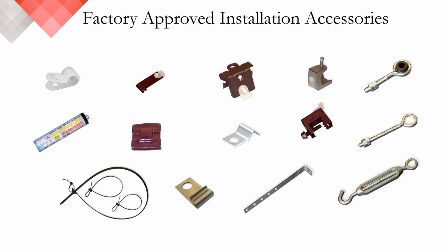The Protectowire company offers an assortment of approved fasteners and splicing devices to facilitate installation for both standard and special applications. Approved fasteners are generally designed to lightly clamp the detector, which enables the tension to be applied progressively. This method is better than arrangements which apply a high tensile load at the end of each run, or clamp and compress the sensor cable so tightly that the inner insulation becomes damaged. To ensure a trouble-free installation, only factory-approved fasteners should be used. The use of non-approved fasteners may physically damage the detector, thereby causing false alarms, and in some cases, void the detector's warranty.